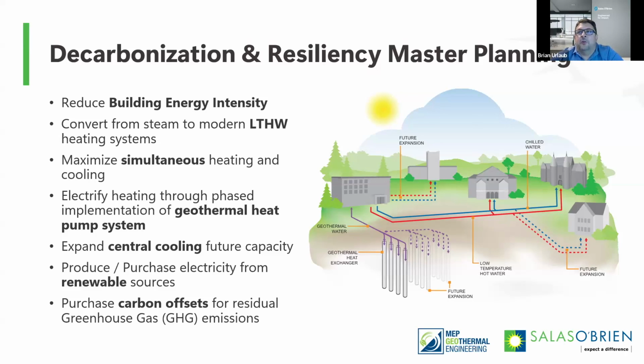The best aquifer for open loop is 1,200 feet in the ground, the Mount Simon. To pump water up 1,200 feet from the surface and then back down 1,200 feet is a massive well, a huge pump, a lot of pump energy, and a tremendous cost. And they have all kinds of space. So why would you put in an open loop that costs that much and goes that deep, when you could do shallow 500-600 foot boreholes and put a thousand of them in, and probably get a lower cost because you don't have to go as deep?